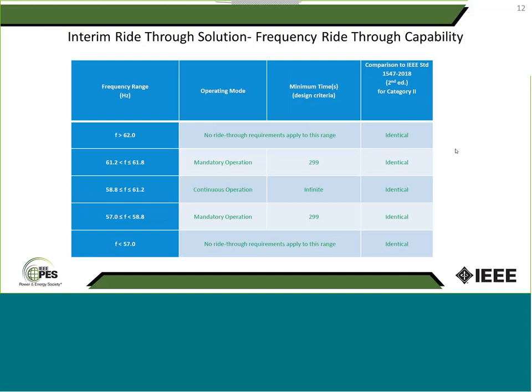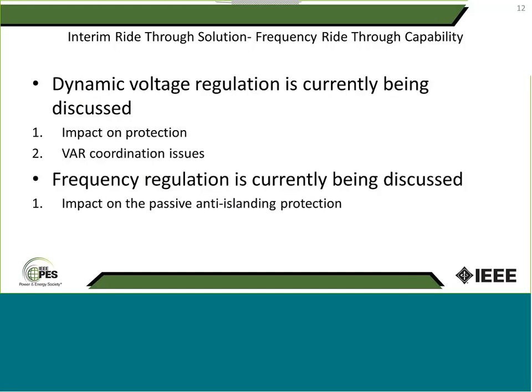And the reason that we don't use frequency measurements for protection is that some relaying manufacturers still use the zero crossing point, and it can be tricked by noise in the system. I know some use advanced phase lock loops, but there are some issues when it comes to utilizing frequency for faults. And when you do have a fault, the system frequency doesn't change much after some transients. It's really not a good relay for fault detection anyway.